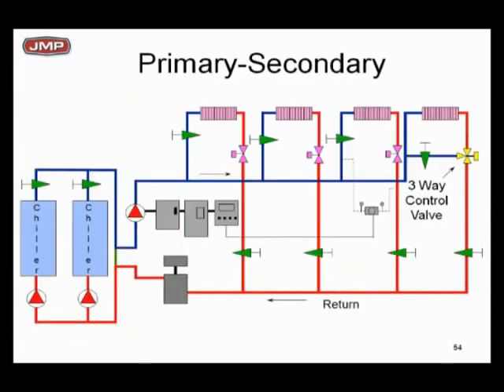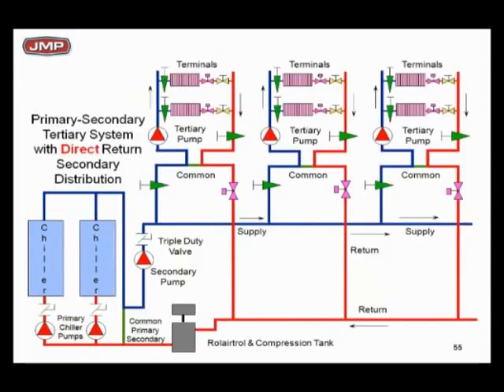Here's a typical primary-secondary system. We've got a dedicated pump for a chiller at constant flow. Again, see the common pipe, and you've got a little secondary pump with two-way valves. Primary-secondary: the secondary is variable flow, the primary is constant flow.